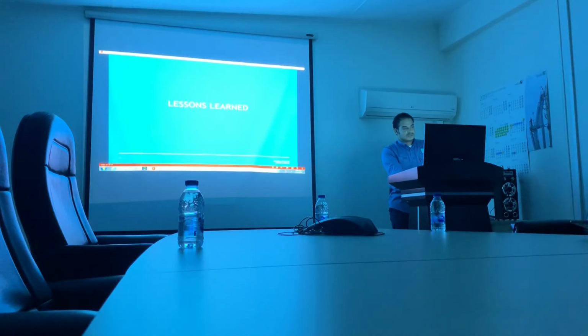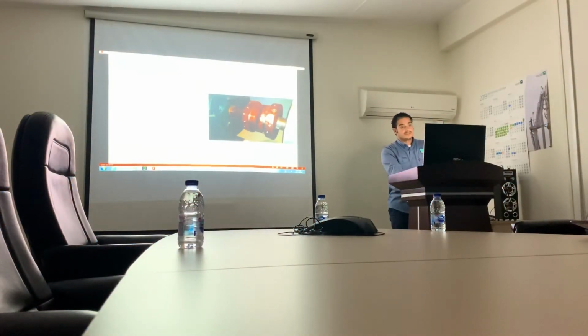We're going to talk about lessons learned. We will give some examples. For example, this pump shaft and motor shaft. Here, the pump coupling was found rusted and the shaft was stuck, preventing the required periodic shaft rotation. Root cause: material receiving inspection was not conducted to verify the preservation condition, and preservation was not initiated for more than 6 months.